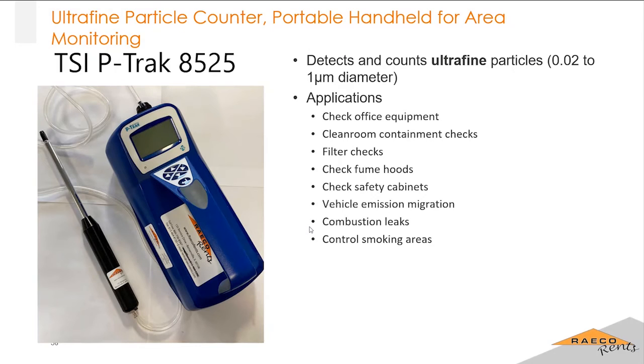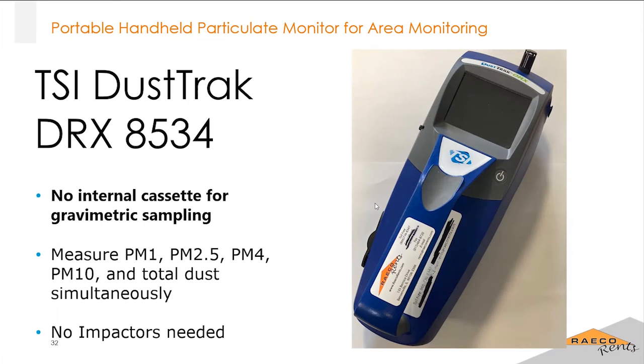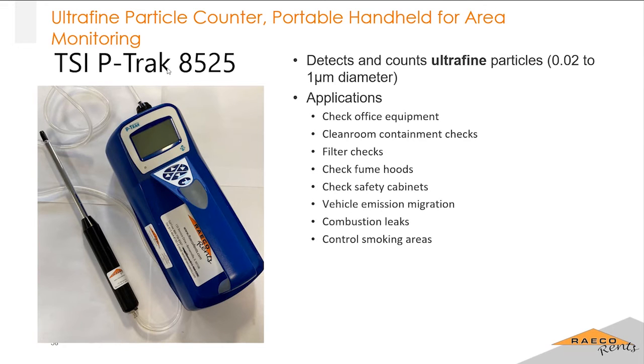Okay, all right. We'll move on to our particle counters. Everything I was showing you before, your DustTrak, your SidePak, these are all measuring in milligrams per cubic meter. And the P-Trak, also made by TSI, is a particle counter. It's just going to give you a count of particles per cubic foot, or I think per liter. It kind of just depends what you're doing. Again, that's a unit that you can set on the instrument. This one's just specifically for ultrafine particles, so pretty much anything smaller than 1 micron. They're most often used in clean rooms, checking fume hoods, making sure there are no leaks in those, combustion leaks, a lot of different stuff.